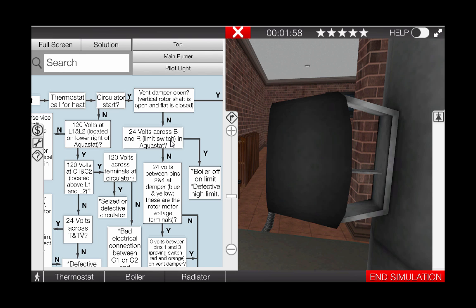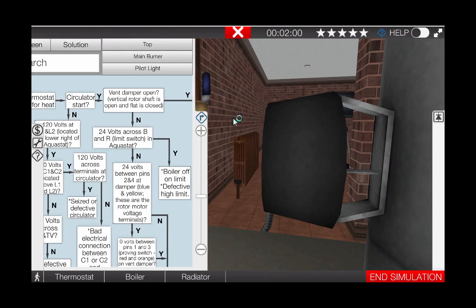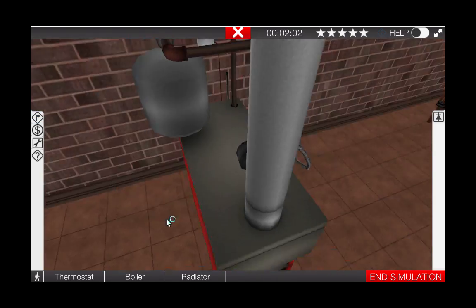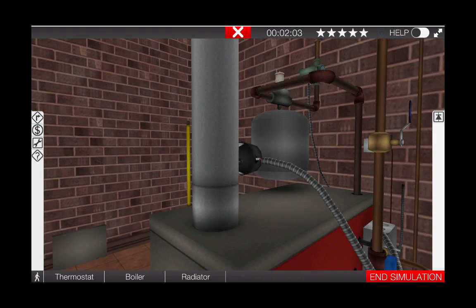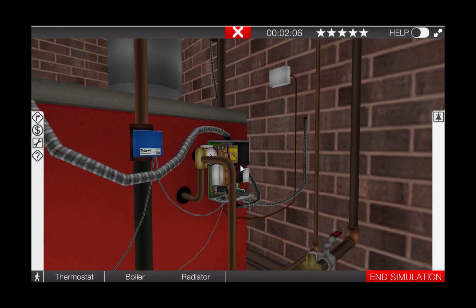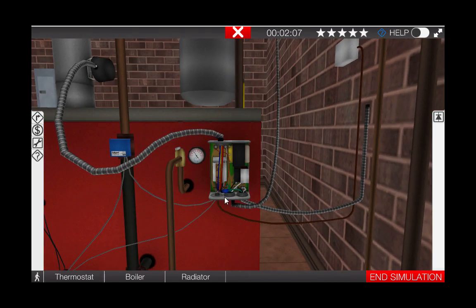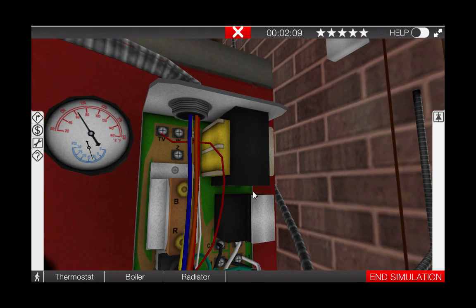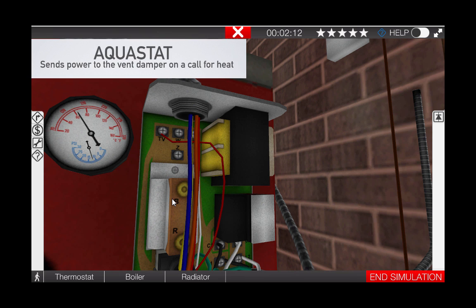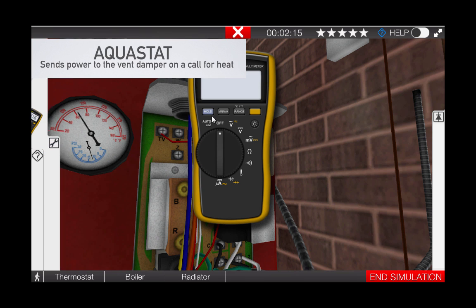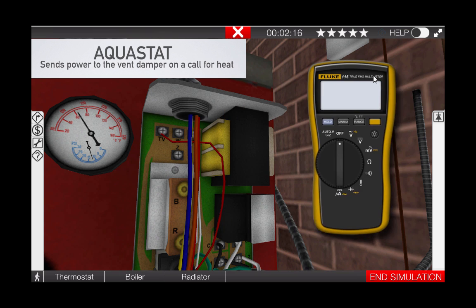Let's check it out. Proceed to the aqua stat and remove the digital multimeter from the toolbox. Removing the cover from the aqua stat and centered in your field of view, zoom in to locate the B and R terminals on the high limit, shown right here.